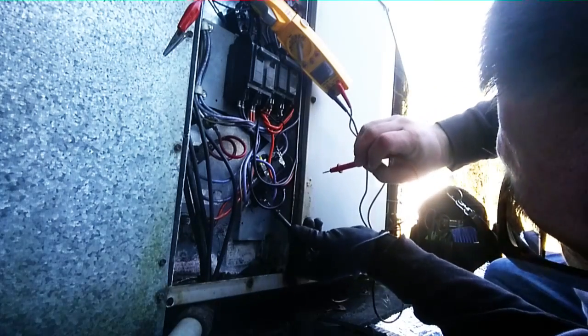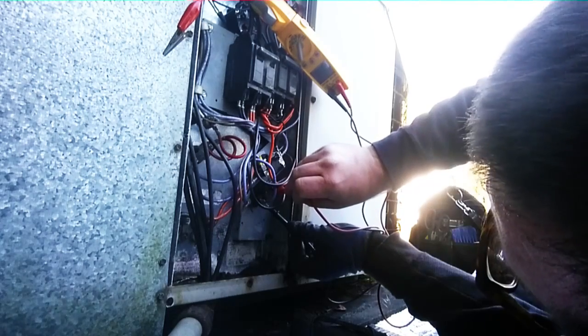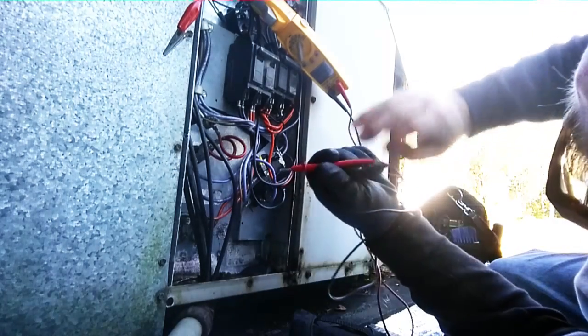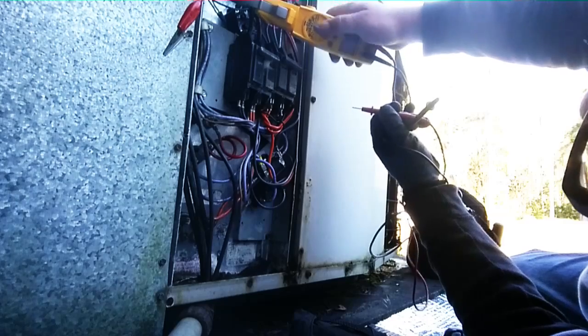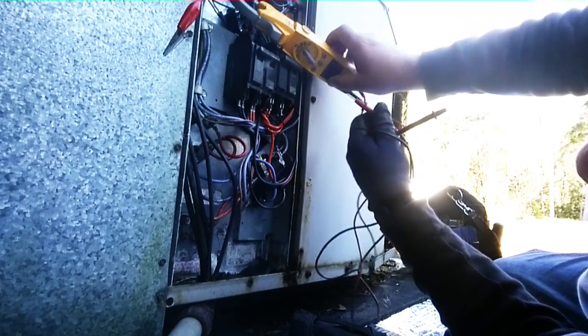On this bottom sequencer — oh, maybe that's it. Yep, they're all pulled in now. 40 amps, 10kW — good to go.